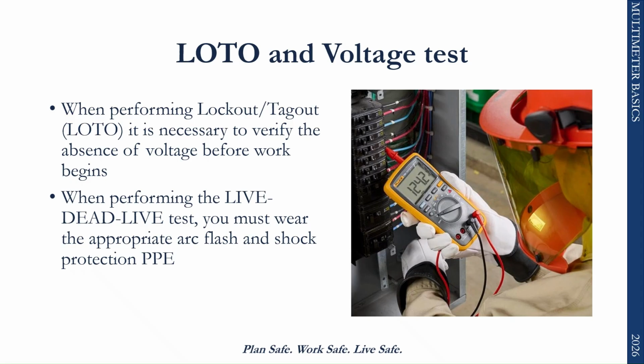When performing lockout-tagout, verifying absence of voltage is a critical step before work begins. Even after equipment has been locked and tagged out, it must still be tested to confirm that no voltage is present. This is where the live-dead-live testing procedure comes into play. It's also important to remember that when performing voltage testing, employees must wear the appropriate arc flash and shock protection PPE for the equipment being tested. Testing does involve exposure to electrical hazards, so proper PPE is required during the verification process.